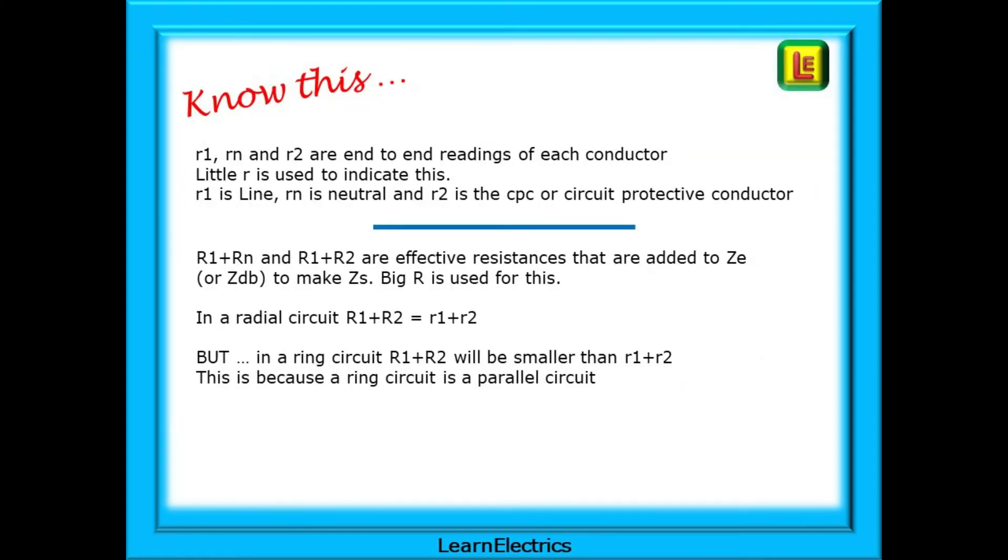To begin with, you must know this. Little R1, little Rn and little R2 are the end-to-end readings of each conductor. Little R is used to indicate this. This is important, it differentiates between the different test results. Little R1 is line, little Rn is neutral and little R2 is the CPC.